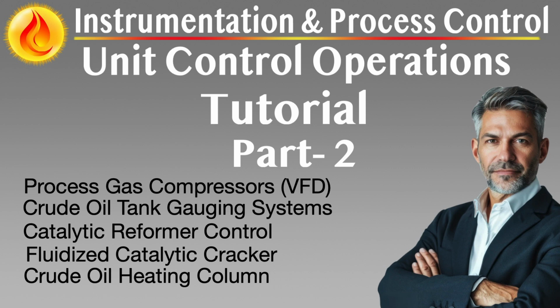Hydrogen management is another critical pillar. Reformers produce large volumes of hydrogen that are routed to hydrotreaters, hydrocrackers, or hydrogen networks. Controlling hydrogen purity, recovery, and system pressure is vital to avoid contamination or off-spec downstream performance. VFD-controlled hydrogen compressors, purge gas monitoring, and hydrogen purity analyzers are commonly integrated into the reformer control strategy. APC layers optimize hydrogen recycle rates to maintain catalyst protection while minimizing hydrogen loss to fuel gas or flare.